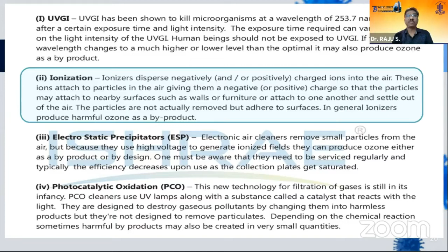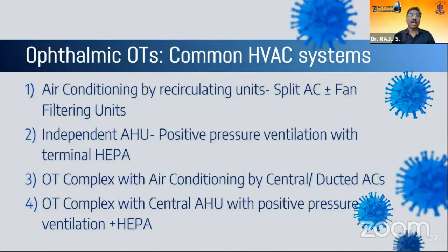Coming to the OT, the most common HVAC systems that we commonly use in ophthalmic setups are the split ACs. They are recirculating units. Fan units can also be added in these OTs. The next commonly used system is the independent air handling units, which are positive pressure ventilation systems with a terminal HEPA. While very big hospitals have an OT complex with central air conditioning which is supplied through ducts, or you may have an OT complex with a central AHU with positive pressure ventilation and HEPA. So these are the various systems that are available for all of us.